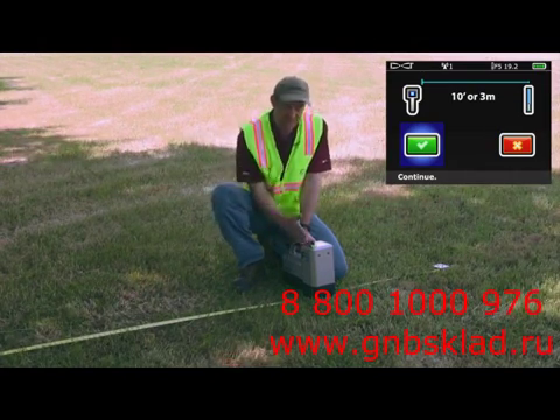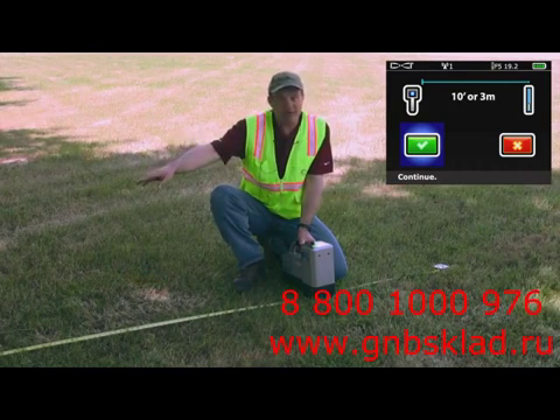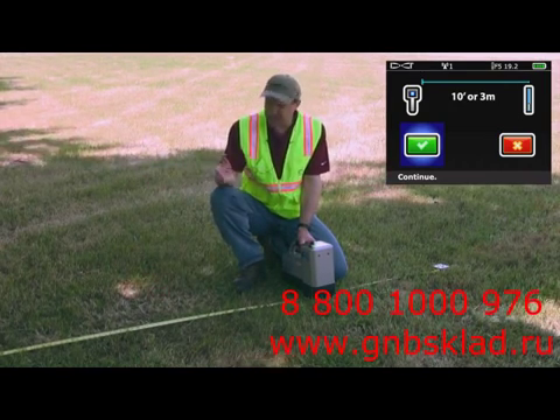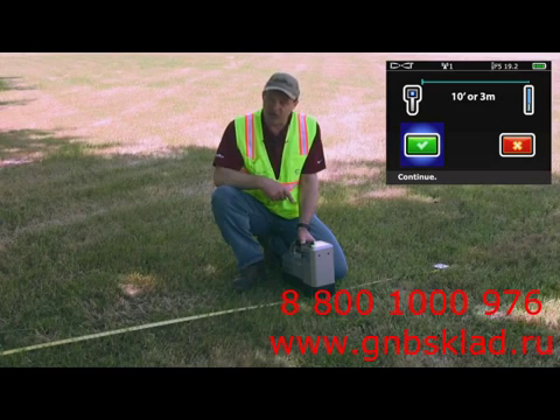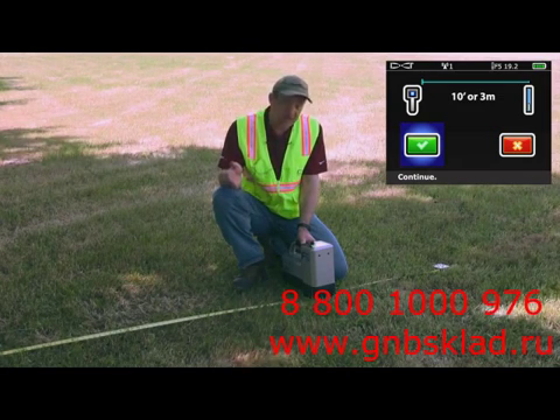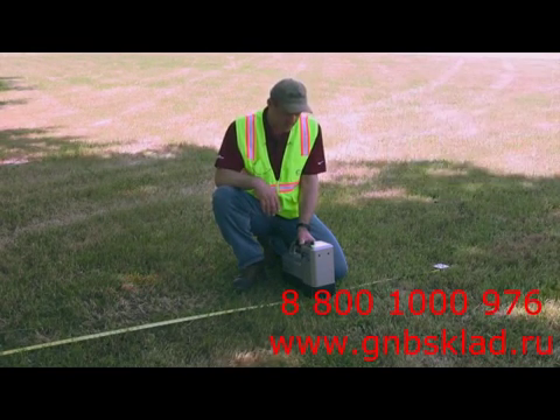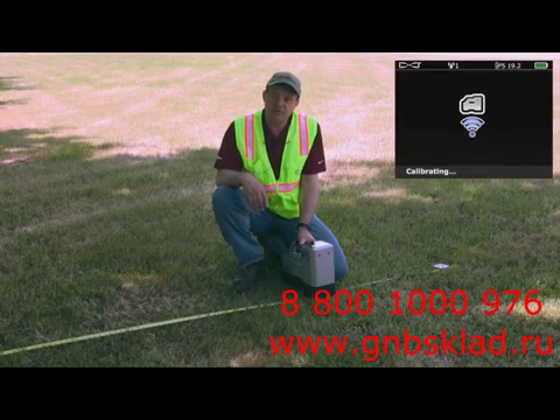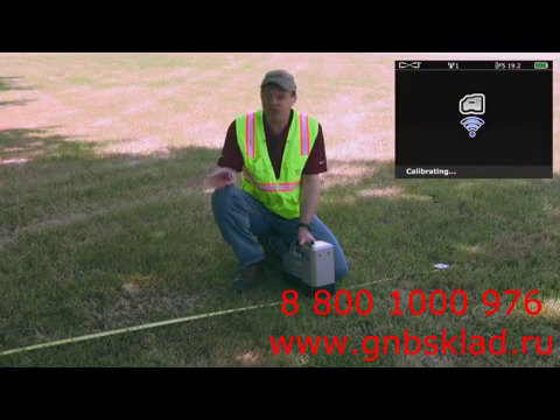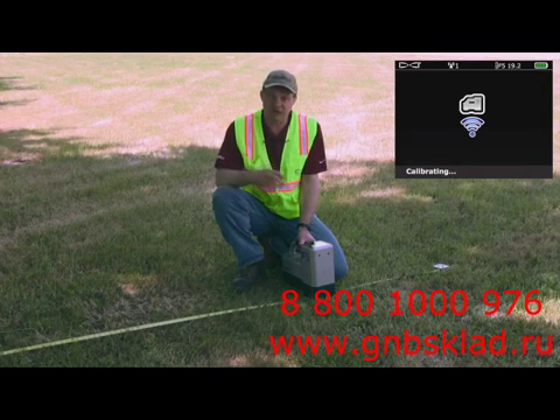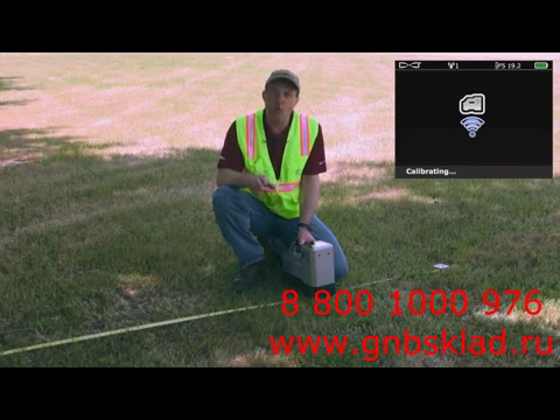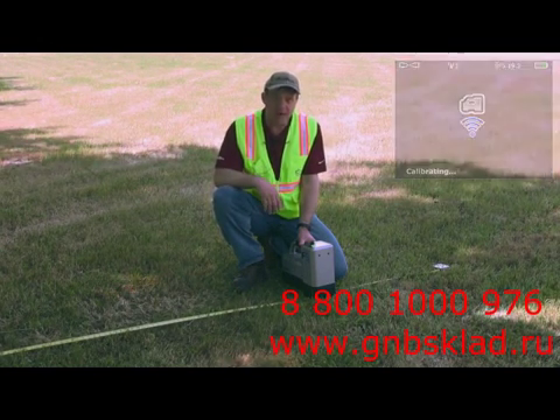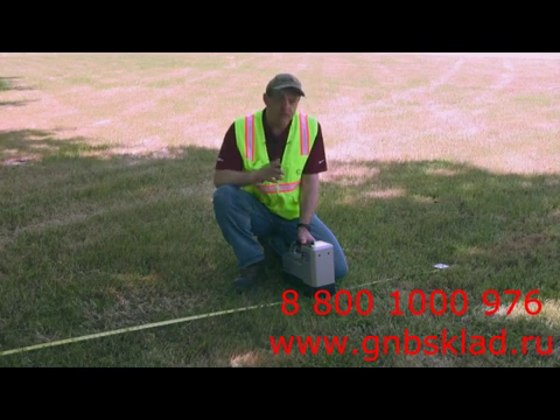Once again, inside edge to the middle of the TensiTrak device. You've got that set up. We know we do. I've got a green check here on my display. You like the way it's set up? And we do. Click the trigger. Takes a couple of seconds. It's measuring its signal strength. It's converting that signal strength to 10 foot or 3 meters, forevermore. So now we're calibrated. It's just that simple.